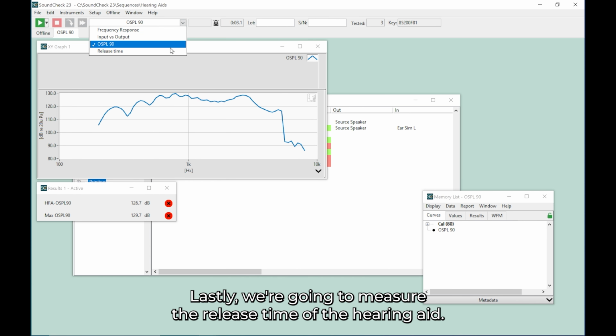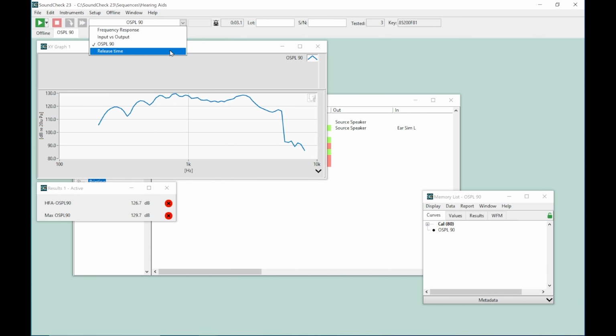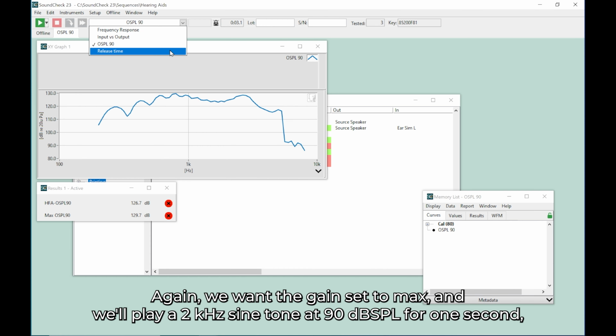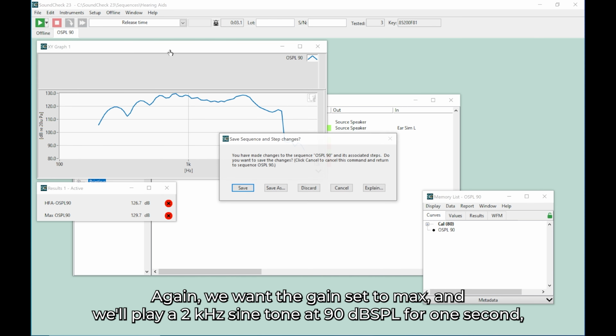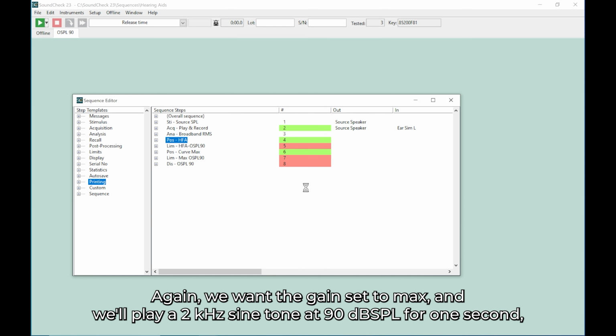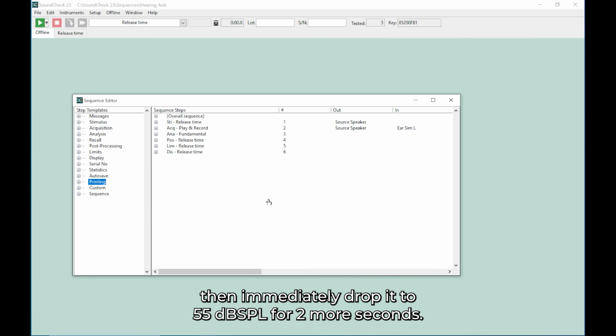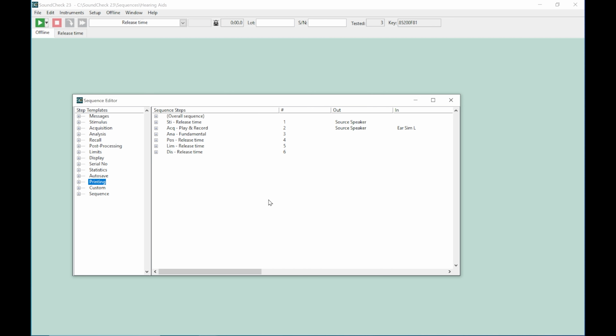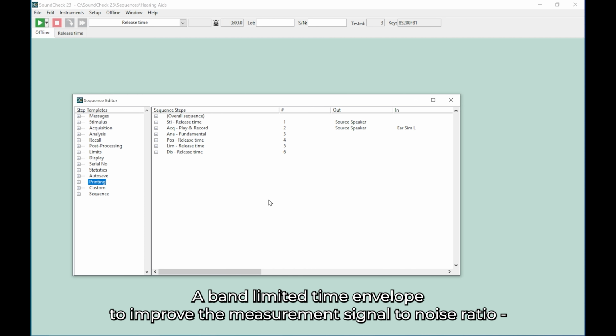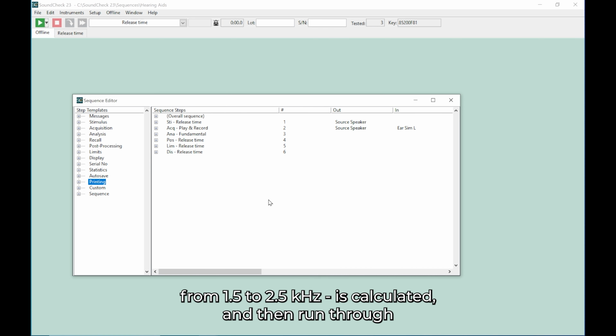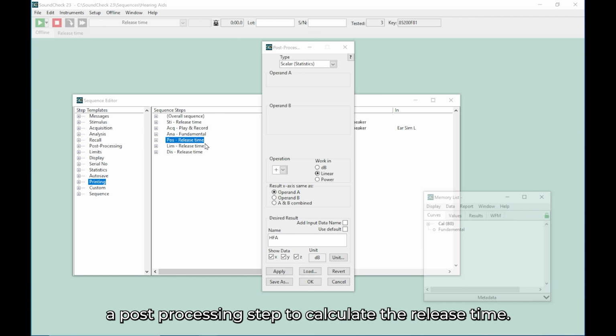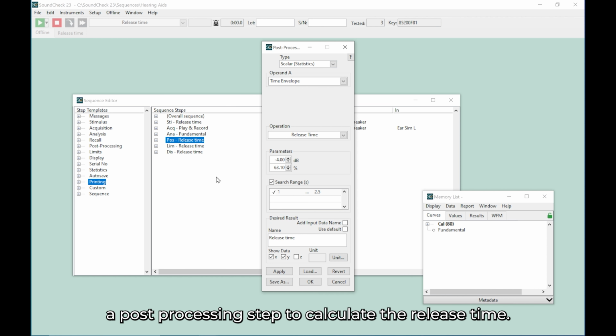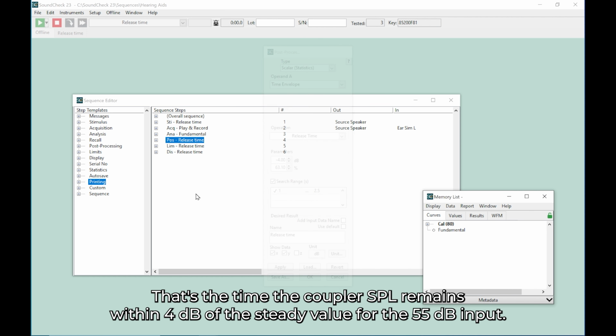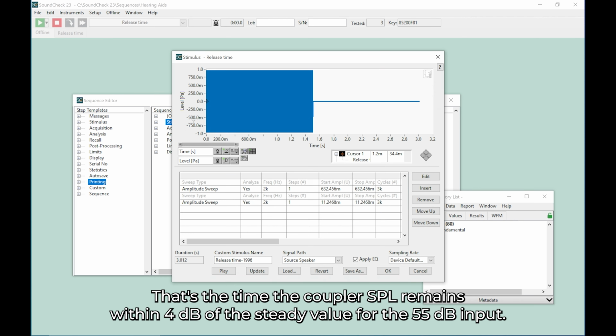Lastly, we're going to measure the release time of the hearing aid. Again, we want the gain set to max, and we'll play a 2 kHz sine tone at 90 dB SPL for 1 second, then immediately drop it to 55 dB SPL for 2 more seconds. A band-limited time envelope to improve the measurement signal-to-noise ratio from 1.5 to 2.5 kHz is calculated and then run through a post-processing step to calculate the release time. That's the time the coupler SPL remains within 4 dB of the steady value for the 55 dB input.